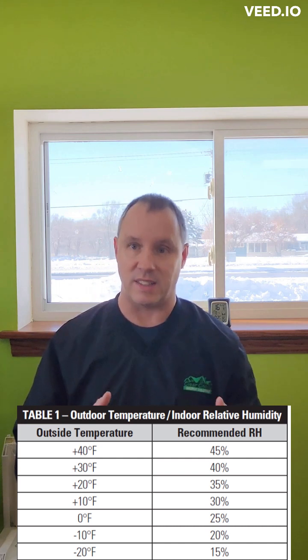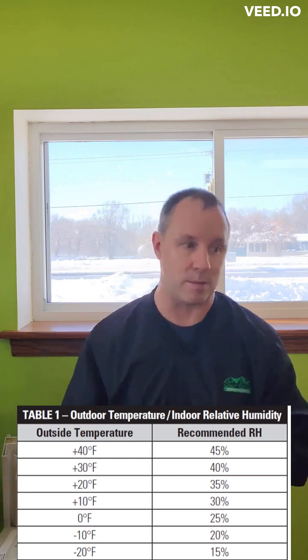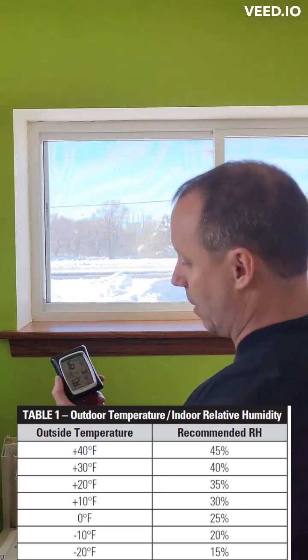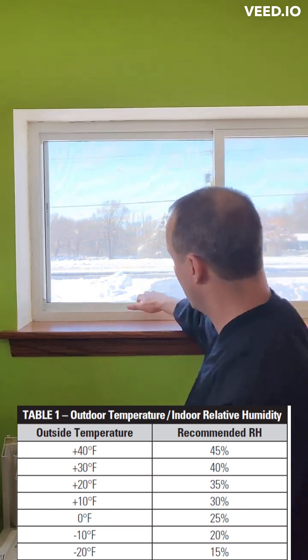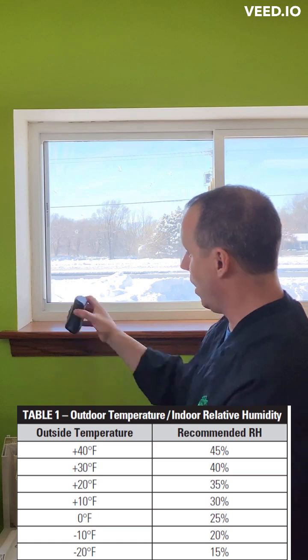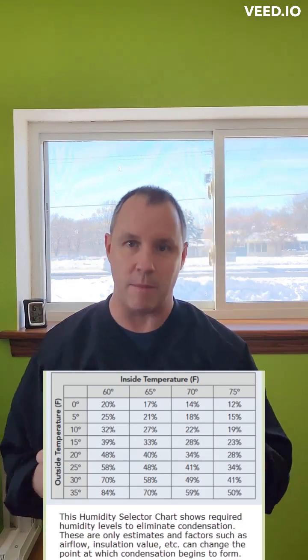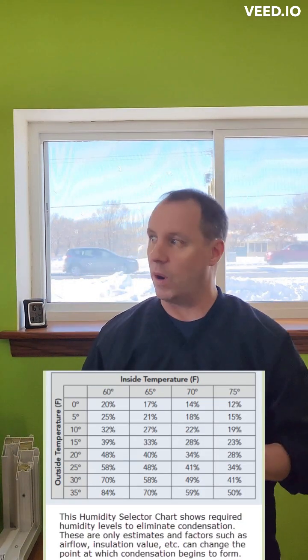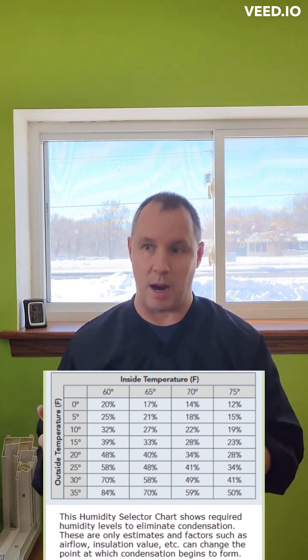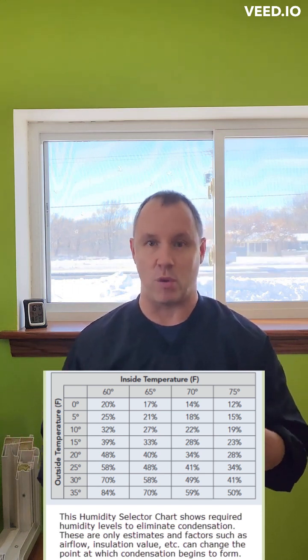So you want to keep that humidity in check. I always tell people once winter gets here, your humidity should never exceed 40%. And as the temperature drops, that humidity should drop with it, even sometimes below 30% if possible. Like our office today, our showroom, we're running about 16 to 20% humidity in here, and you'll notice there's no condensation.